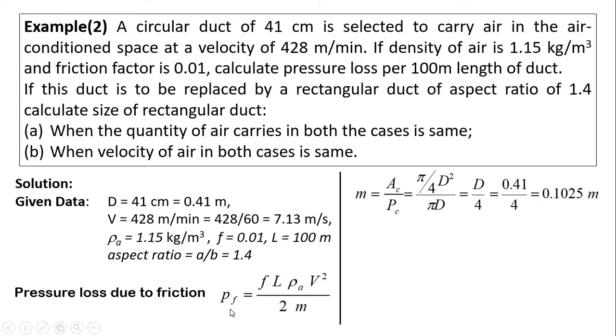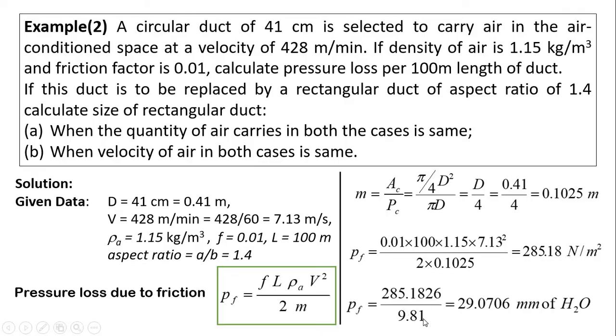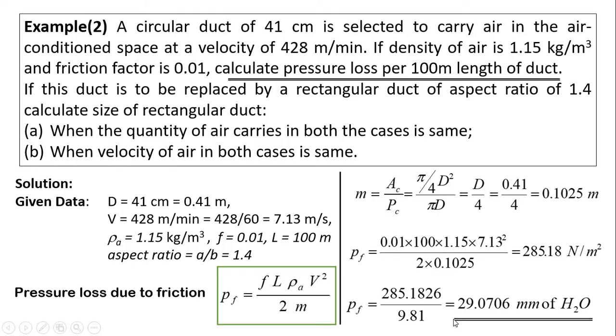Now all values are known. By putting all parameters into the formula, pressure loss due to friction Pf = 285.18 N/m². Converting to mm of water column by dividing by 9.81, we get Pf = 29.07 mm of water column. So in this way we can calculate pressure loss due to friction for a given circular duct.